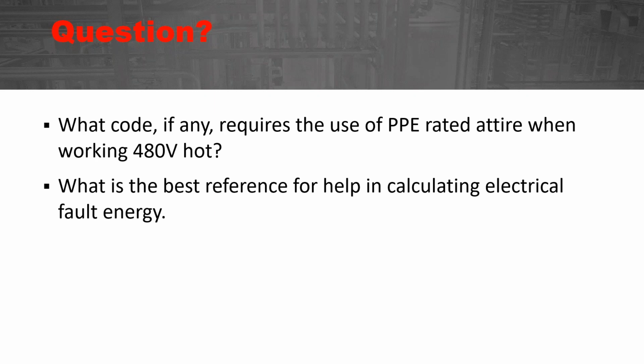If it's DC calculations, there are also some IEEE papers that go into DC arc flash versus AC arc flash. There's also the Ralph Lee method, the Dan Doan method. There are a number of methods out there, and IEEE 1584 does provide some guidance on that in the annex/appendix material. Okay. Thanks, Jez.